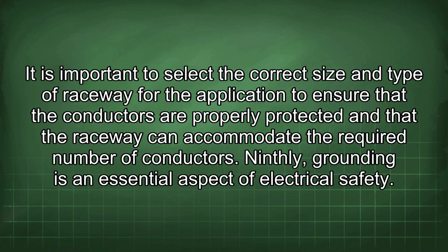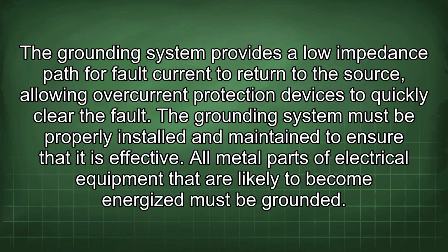Ninthly, grounding is an essential aspect of electrical safety. The grounding system provides a lower impedance path for fault current to return to the source, allowing overcurrent protection devices to quickly clear the faults. The grounding system must be properly installed and maintained to ensure that it is effective. All metal parts of electrical equipment that are likely to become energized must be grounded.